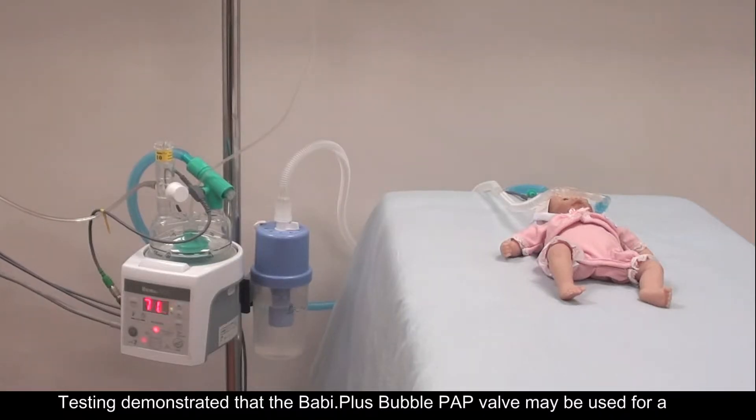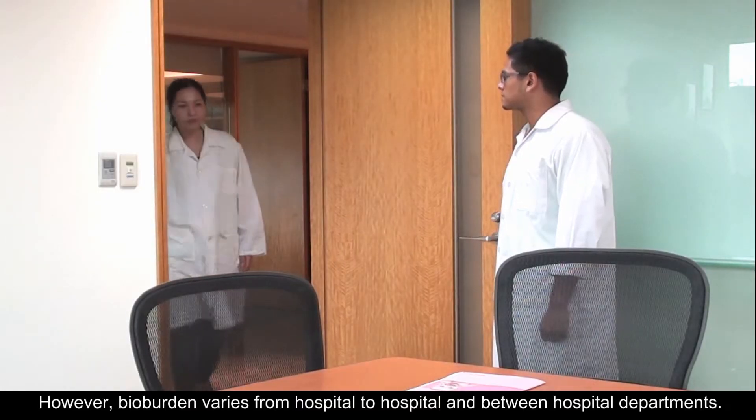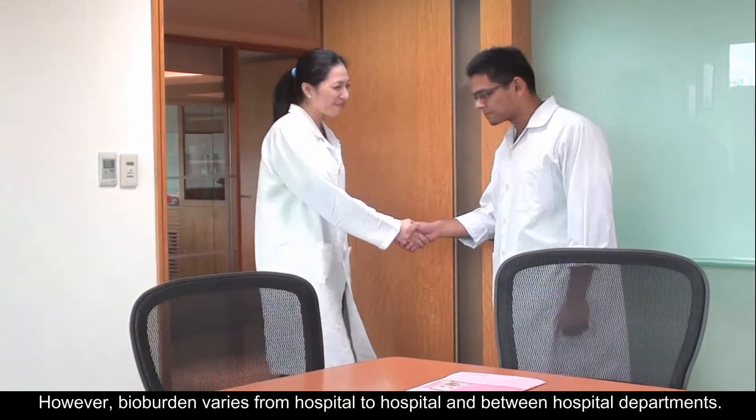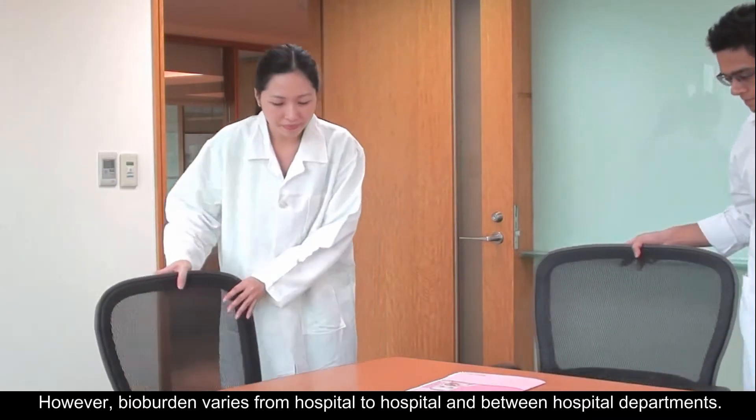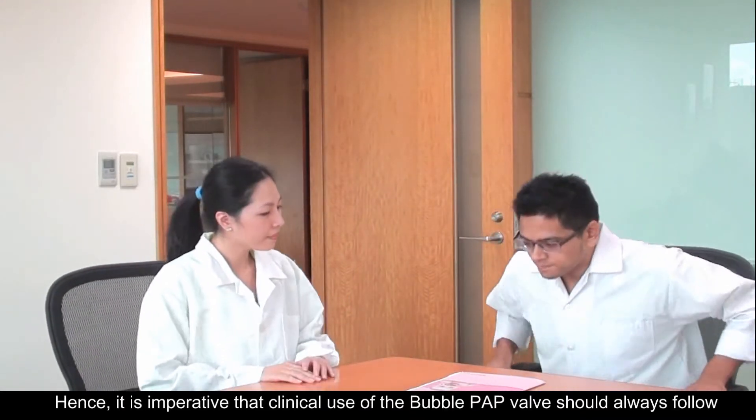Testing demonstrated that the Babi.Plus Bubble PAP valve may be used for a maximum service life of 28 days without mechanical failure.